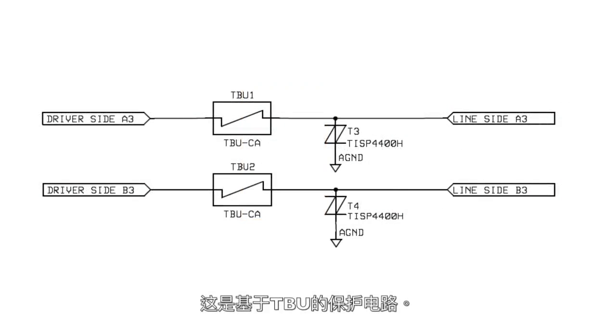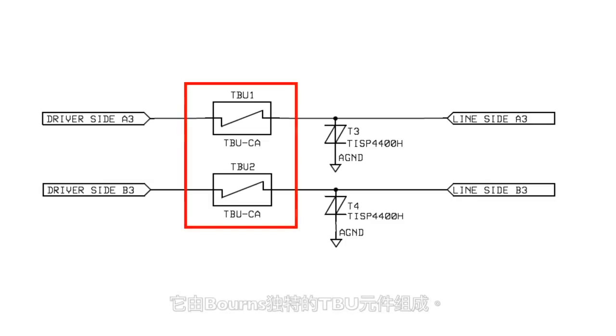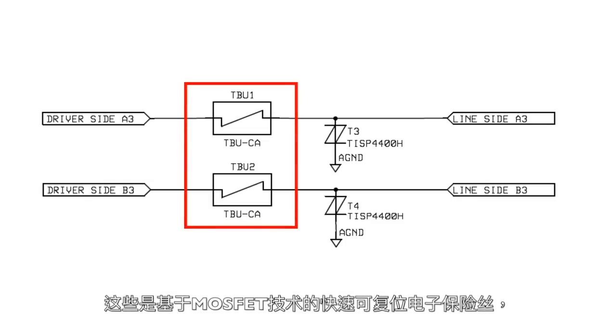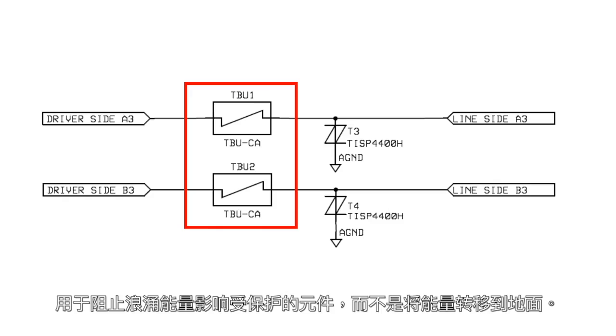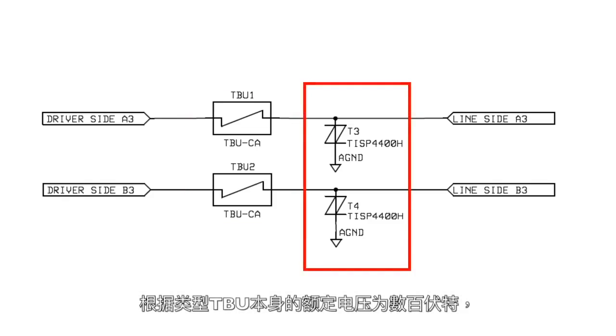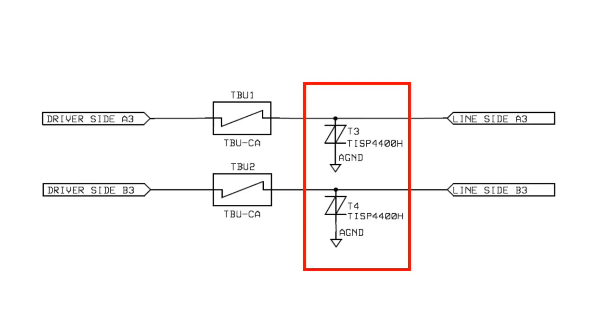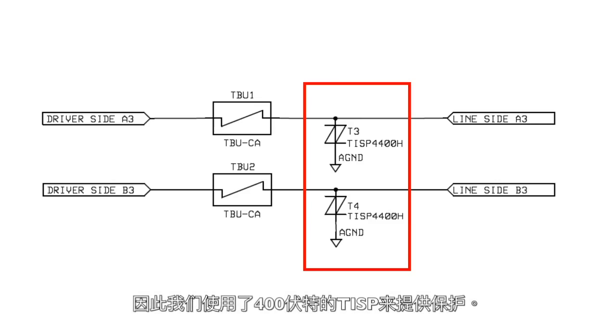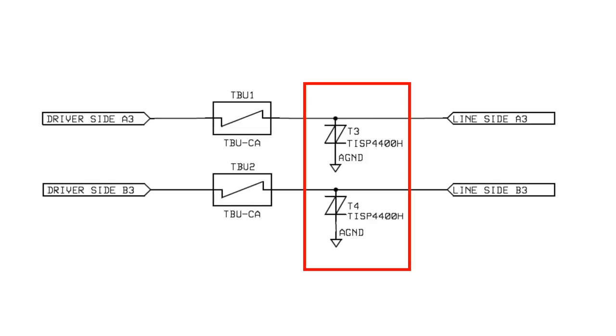This is the TBU-based protection circuit. It consists of Bourns' unique TBU devices. These are fast resettable electronic fuses based on MOSFET technology that block the surge energy from reaching the protected component rather than diverting the energy to ground. The TBU itself is rated to several hundred volts according to the device type, but it needs to be protected from any voltage larger than that, and so we've used a 400V TISP to provide that protection.